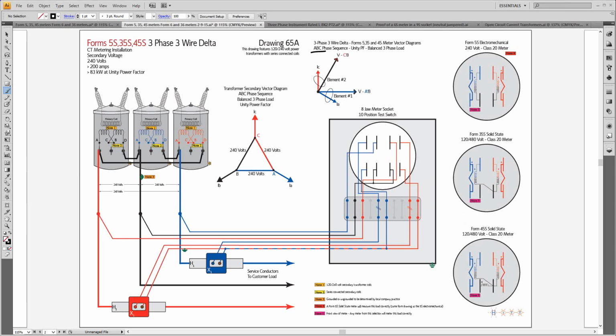Yeah, in Seattle, like I say, south of downtown, and it would start about where the stadiums are and go south from there. There's a large industrial area in there, and lots of that is three-phase, 3 or 4-wire delta, with a lot more 4-wire delta than 3-wire delta, but still, there's enough 3-wire delta out there that we still have to take care of. So, any other questions on this?